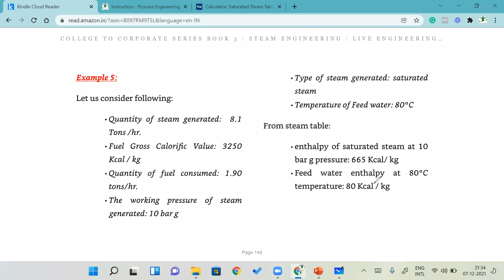Okay, so these things are required, and here there is a small example. The enthalpy of saturated steam and many other things are there, and based on that they calculated around 76%. Most of the time it was coming between 70 and 80%. In a direct method, what will happen? We are just calculating the heat output divided by the heat input, into 100. Nothing else is happening. Because of that, there are many disadvantages.